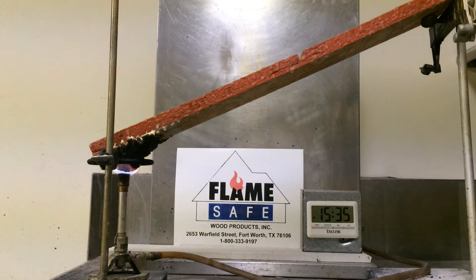The important thing to recognize about the ASTM D3806 test is that it also takes into consideration the mass loss of the specimen. The reason why this is important is to show you that there is no structural loss to the specimen being burned — that's important for engineers when they're engineering buildings.